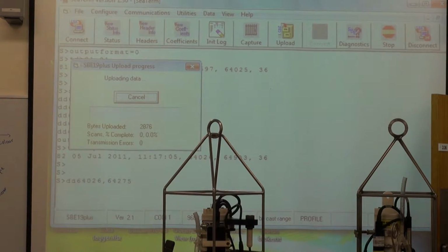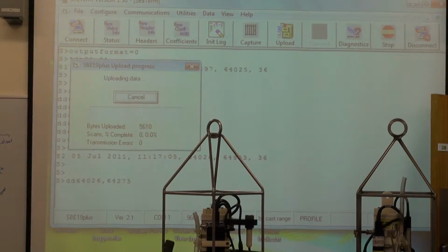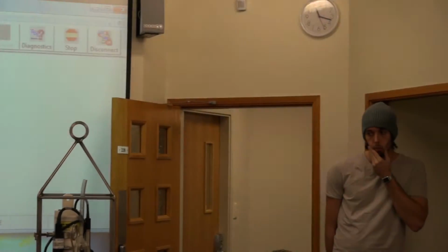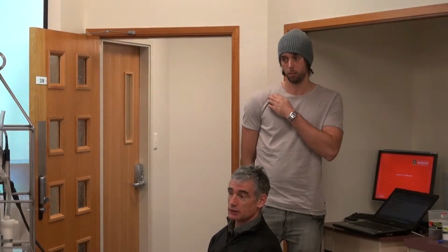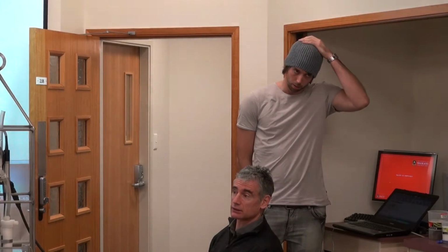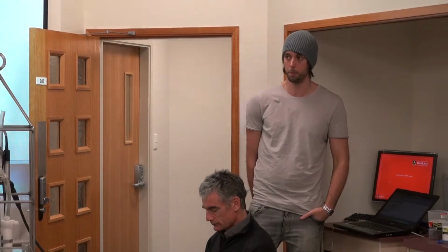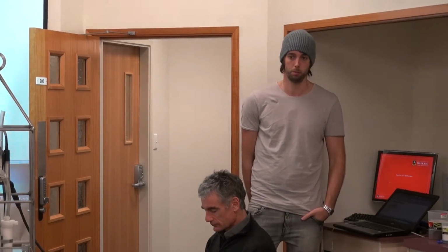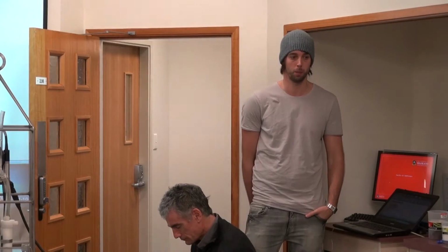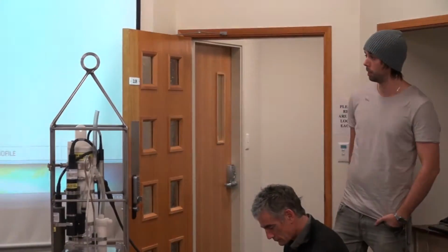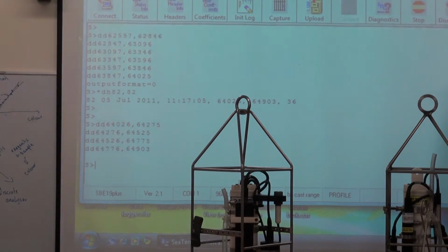And are these mostly used in lakes and all the big waters type systems? Well, most people tend to use them at some stage. What do you mean, CTDs? Oh, absolutely standard oceanographic equipment and top of the range, really. The sensors are a lot more stable than some of those other instruments that we've seen, so calibration is probably more the concern of techs around here rather than students who want to take the picture. But if you want good data, it's always worth checking the instruments calibrated recently.